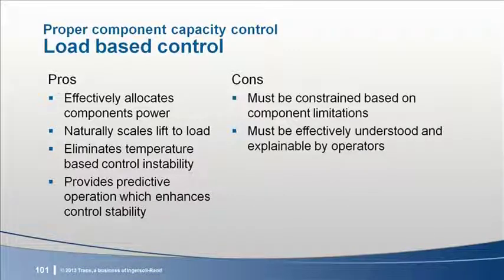However, it does not come without other challenges. This form of control, if not constrained properly, can and will drive one or another component into an unacceptable operating region. Mick will discuss component operating limitations in just a moment. Suffice to say that it is imperative that an implementer of this control method have a thorough understanding of each specific component so that the control sequence can be properly constrained. We don't want to overstate this requirement. Every control method comes with constraints, but since this is new and an unfamiliar control method, it is important that these be understood by the implementer as well as the operator.